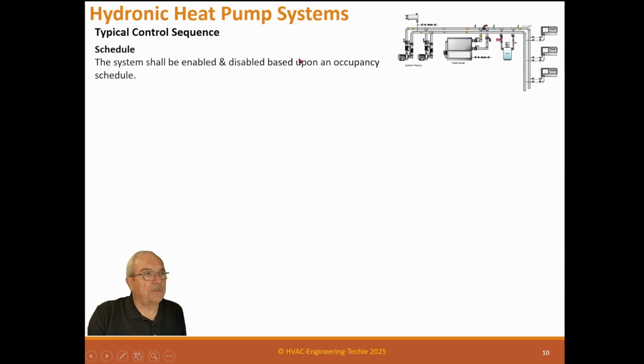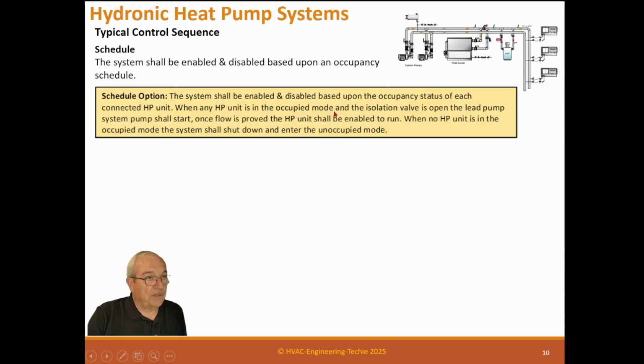All right, sequence. The system should be enabled and disabled based upon an occupancy schedule, just like the other one. Same, we can have this schedule option. We can have the system start just like the other one. So the system shall be enabled and disabled based upon an occupancy status of each heat pump unit.